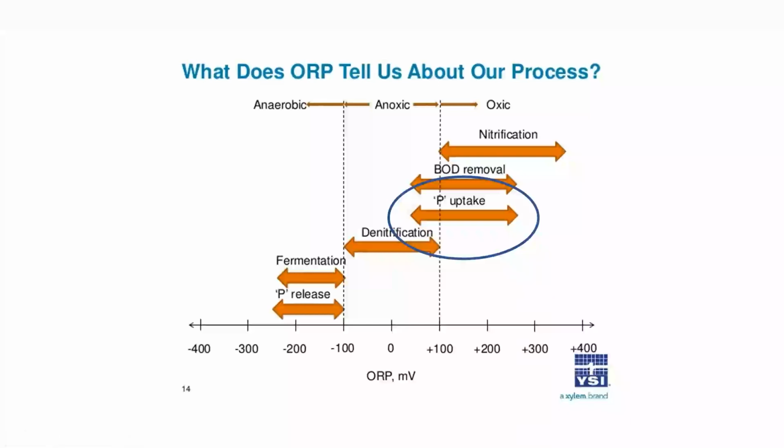Sometimes in some plants, it seems to me, and this is a Grant Weaver observation, a Grant Weaver theory, I don't think you'll find it anywhere else, so consider that when you pursue this next thing I'm about to say. But I've found that in some treatment plants that have a lot of anoxic and anaerobic zones ahead of the aeration, they can chew up so much BOD that there just isn't enough BOD to grow these energized organisms. So that's something I'll talk about at the very end of my presentation today.